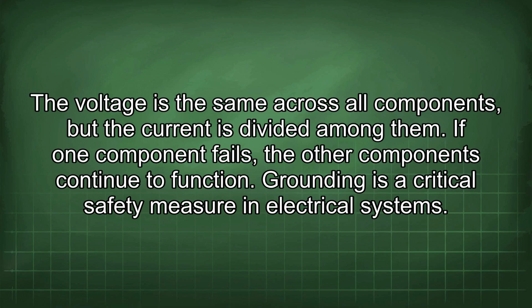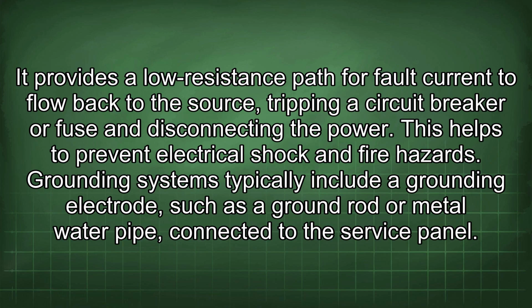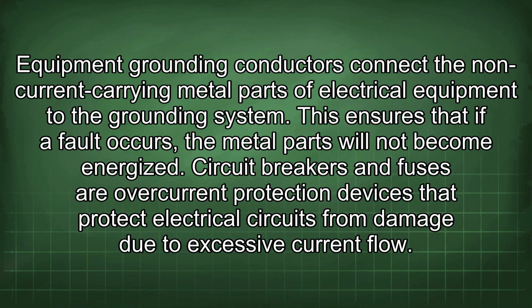Grounding is a critical safety measure in electrical systems. It provides a low resistance path for fault current to flow back to the source, tripping a circuit breaker or fuse and disconnecting the power. This helps to prevent electrical shock and fire hazards. Grounding systems typically include a grounding electrode, such as a ground rod or metal water pipe, connected to the service panel. Equipment grounding conductors connect the non-current carrying metal parts of electrical equipment to the grounding system. This ensures that if a fault occurs, the metal parts will not become energized.